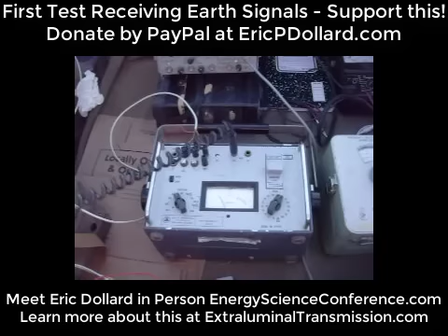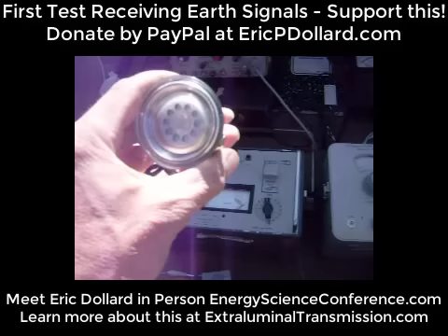So we're running a noise level of 50 decibels, reference noise, which is minus 90 decibels. So we're running about 40, a little bit of pickup there, about minus 40 decibels with reference to a milliwatt, which is about what we receive down on this level here. So the power line noise is 50 decibels stronger than the signal we're trying to receive, which makes it appear futile, but there are methods we could use. So here's the sound - that's the electrostatic field generated by the power line.